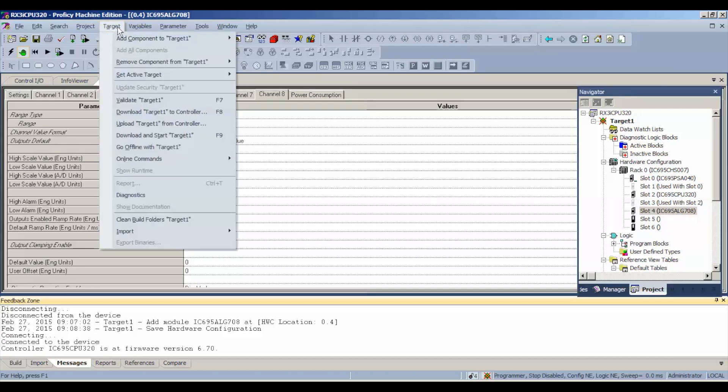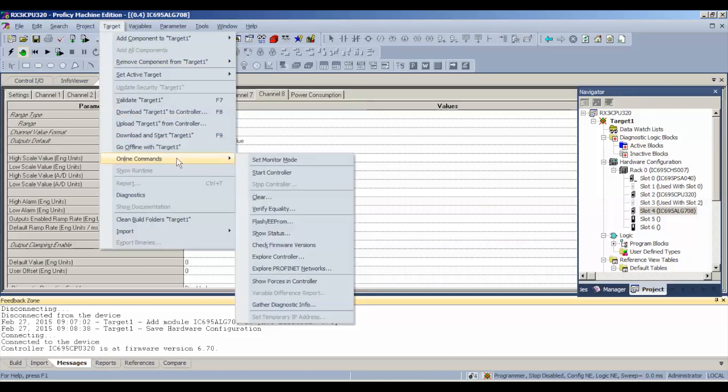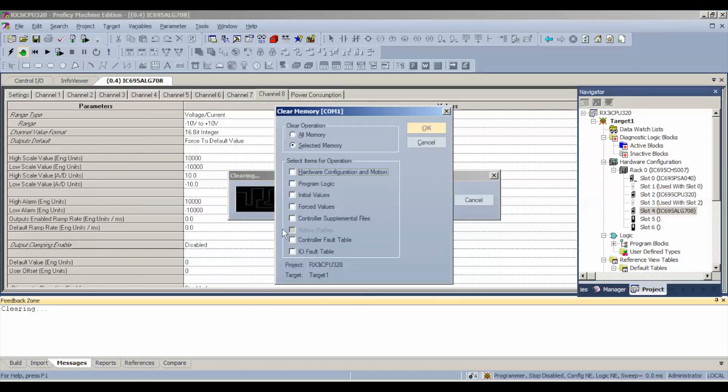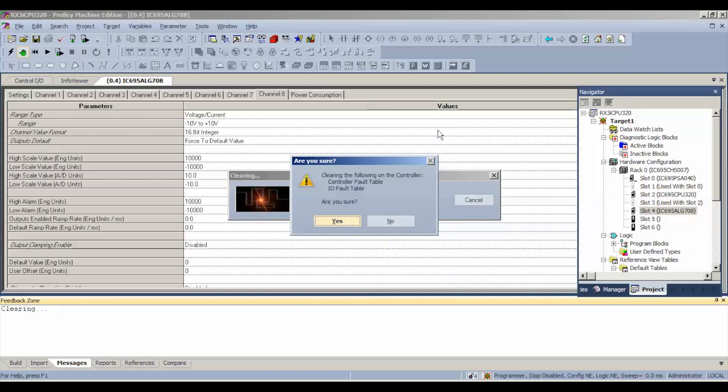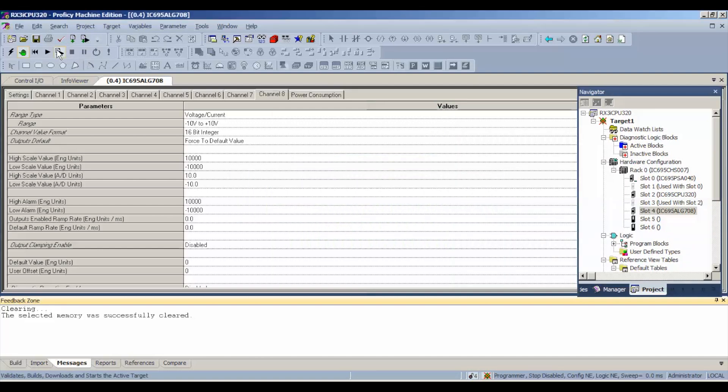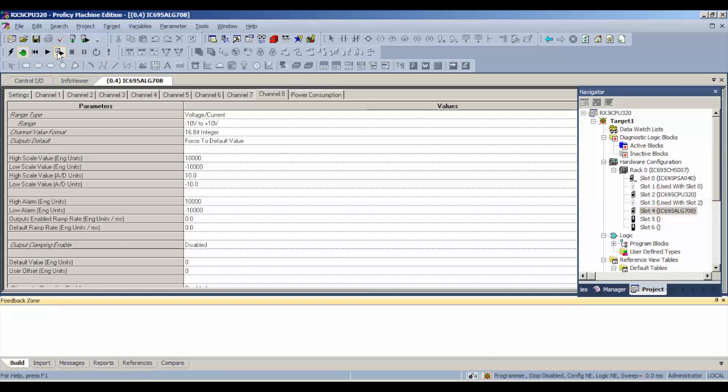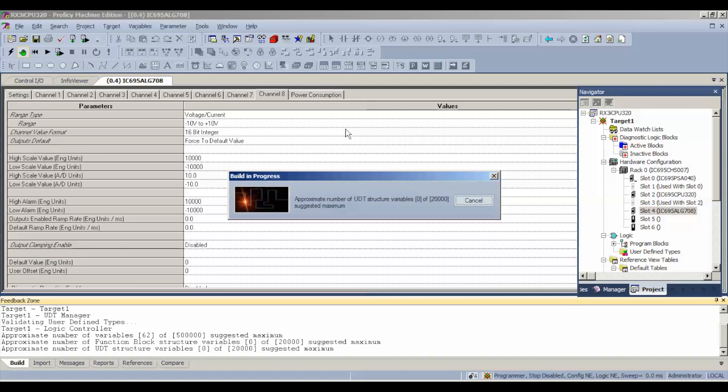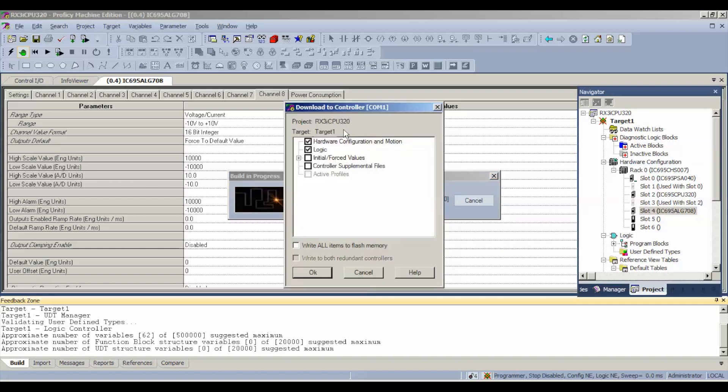We want to go to target and then to online commands and clear and we want to clear the bottom two selections which is controller fault table and IO fault table. This will keep us from getting hung up when we go through the download which we're going to do right now, download and start active target. Very important that you clear those two because you will get stopped and it will create a fault or an error if you don't do that.